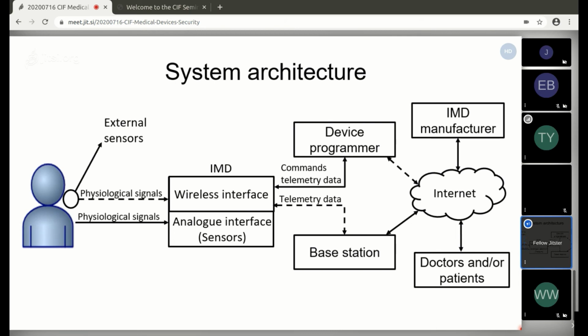Obviously, the implantable medical device also has several internal sensors which are used to constantly measure these physiological signals in the body, and that enable it to detect abnormal situations and actuate accordingly. So, for example, if you think about a pacemaker, all these sensors allow the pacemaker to know when it should deliver a shock to the patient because the heart is not working well. So having explained this, it's clear that there are two ways to attack an implantable medical device. Basically, what the adversary can do is exploit the two entry points. One of them is the wireless interface, and the other one is the analog interface.